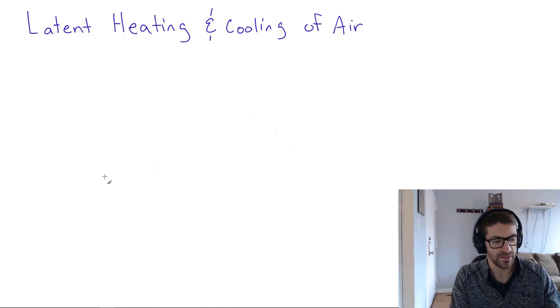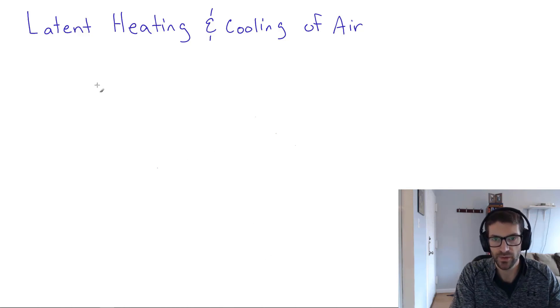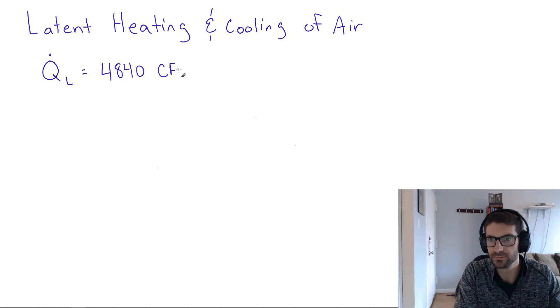And the rule of thumb is lesser known, but equally useful. Might not be a bad idea to memorize this one as well. And it says that the latent heating or cooling is equal to 4,840 times the CFM times the change in not temperature, but humidity ratio.